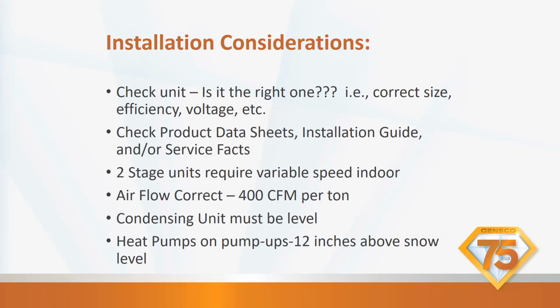And this goes for the office people and the salesmen. They need to make sure that they're putting on the correct equipment at the job site. I've had a few lately where they're putting three-phase into apartment buildings and things like that. So we need to be careful that we're getting the correct voltages of the equipment. Don't assume. Look at the old equipment or look at the actual panels before you buy the equipment. Check the product data sheets, the installation guides, and the service facts for install related issues before you install it.